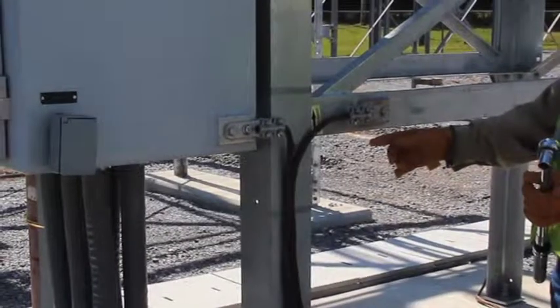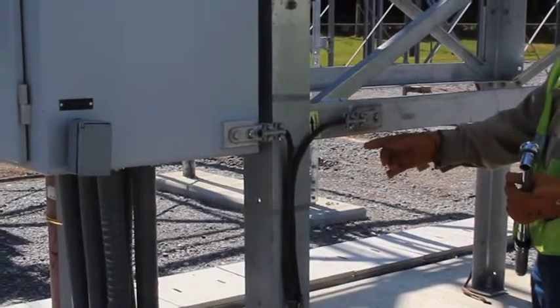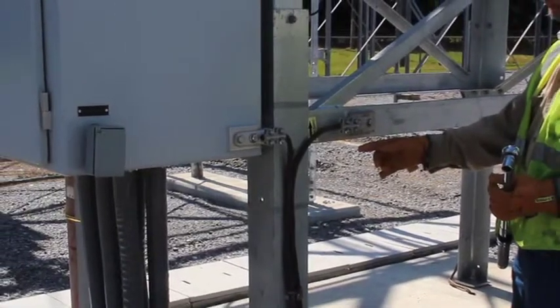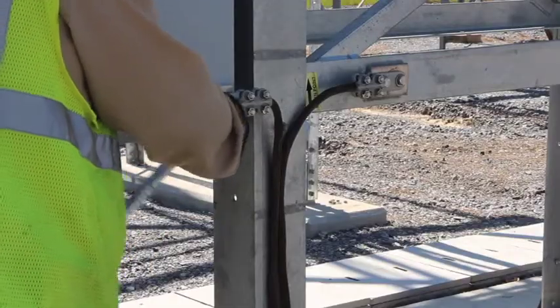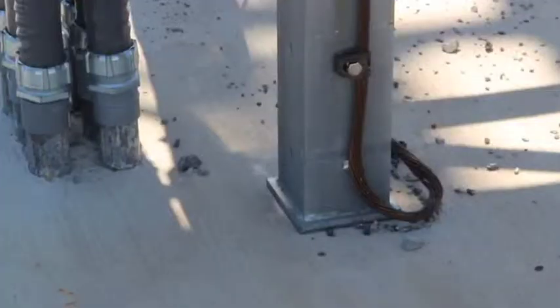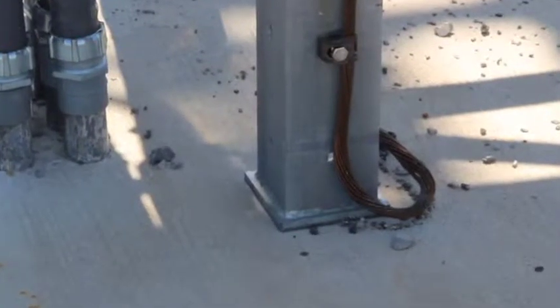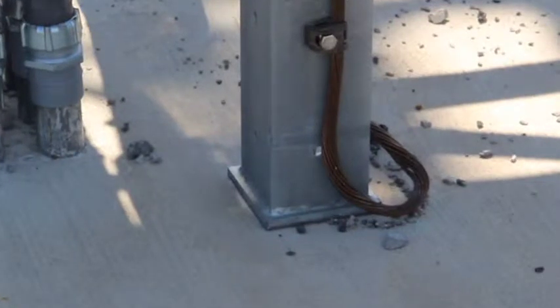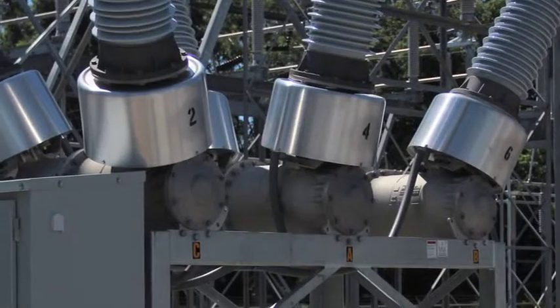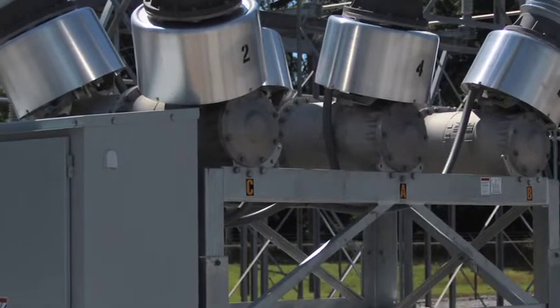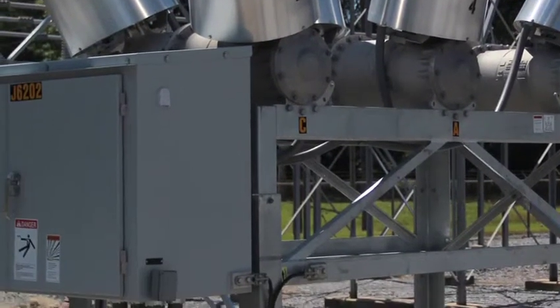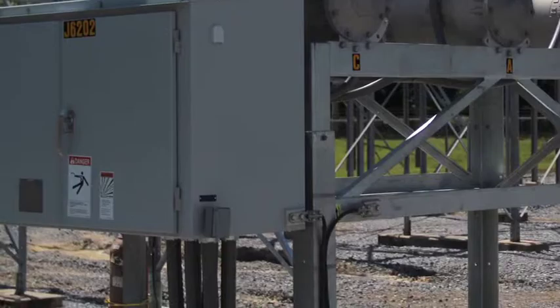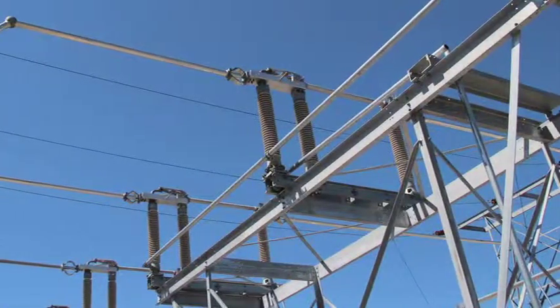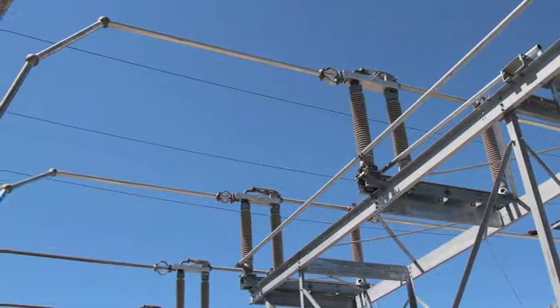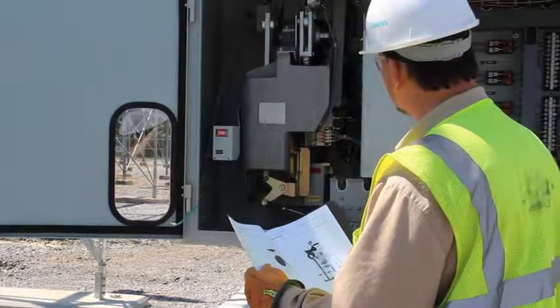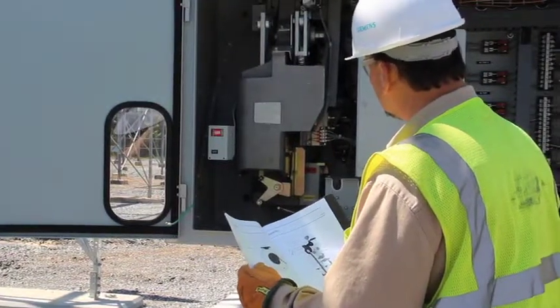2 NEMA standard ground pads are located on the breaker frame, one on the left side and one on the right side. 1 NEMA standard ground pad is located on the cabinet. A connection should be made from these pads to the station grounding network. All joints must be cleaned, bright, and free from burrs or surface roughness. The grounding conductors should be capable of carrying the maximum short circuit current for the duration of the fault. Control wiring and current transformer wiring can now be attached. Refer to the diagram located in the pocket inside the control cabinet door.